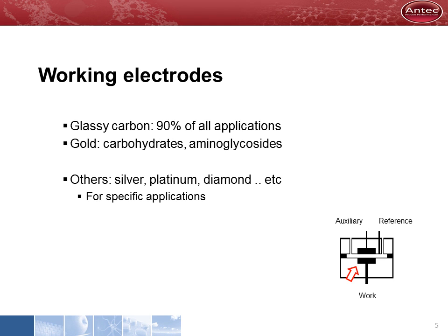There are several different types of working electrodes. The most commonly used electrode material is glassy carbon. It is a highly inert and stable electrode material, compatible with most HPLC solvents and easily polished into a smooth and shiny surface. Other electrode materials are gold, silver, platinum and diamond, which all have specific applications.